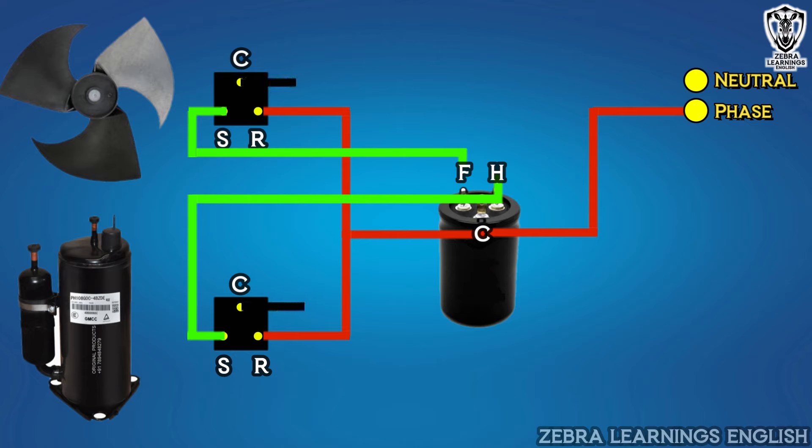Then, the common terminal of the compressor and fan motor should be connected to phase. That's the dual capacitor wiring diagram of an AC unit.